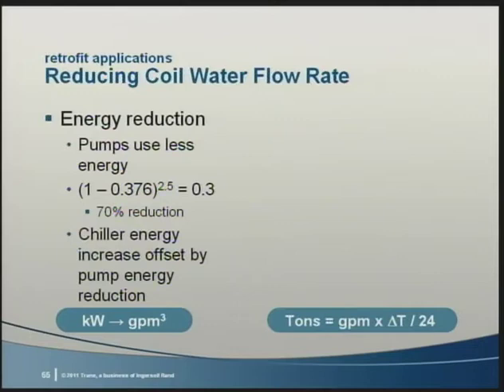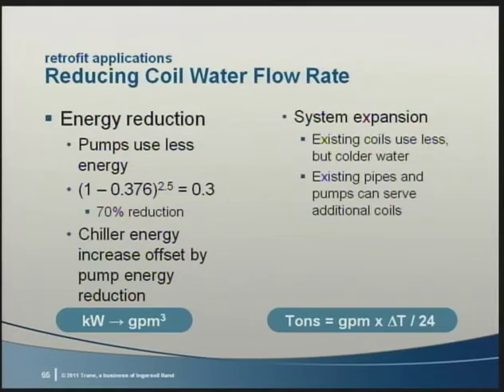energy savings. There are also other possible advantages for system expansion made available by reducing the chilled water supply temperature to existing coils. Let's say that an addition is planned and we want to use the existing chilled water pipes and pumps. By reducing the flow to the existing portion of the building, the rest of the flow can be used by the addition. We'll see in this next example how this concept allows project teams to increase capacity of their pumps and pipes by more than 50%. And this isn't just theoretical.